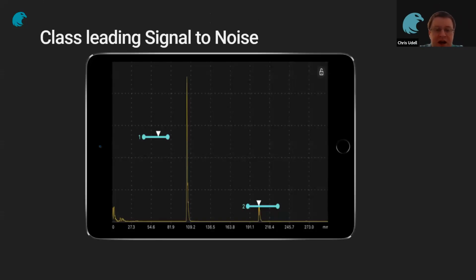Here's an example of the excellent signal to noise. This is on a V2 block using a 70-degree probe. You can see even up to nearly 300 millimeters, you've got zero noise. This is because we've used the best in class low noise amplifiers. We've got the perfect square wave pulsar, so you can really get some excellent signals out of there, which helps you to resolve tips better and to inspect more difficult materials. We've benchmarked this against other systems, and it's class leading on the signal to noise.